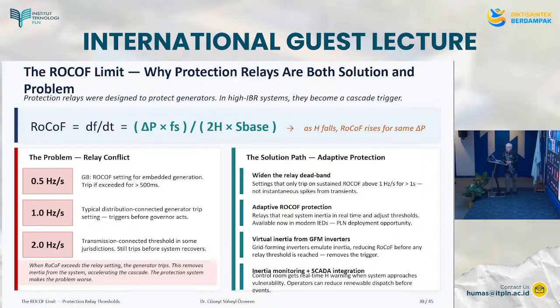Now that is why in the new system we've got to be very careful how we set the relays, and maybe have seasonal settings, because the relays can conflict. The rate of frequency change setting for embedded generation is 0.5 Hz per second. Trip if exceeded for time duration longer than 500 milliseconds.